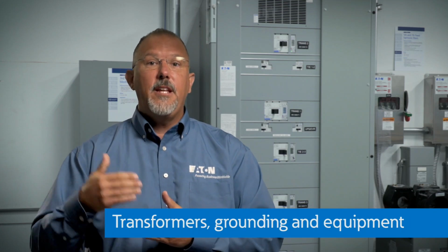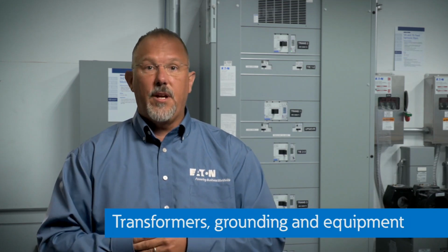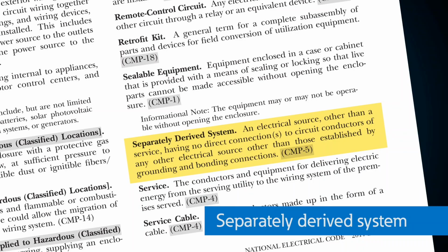Now we're going to move over to transformers for grounding and bonding inside of transformers. When we move into a transformer, we're talking more like a separately derived system. This is your electrical source, other than a service, having no direct connections to circuit conductors of any other electrical source other than those established by grounding and bonding connections. That's your separately derived source.